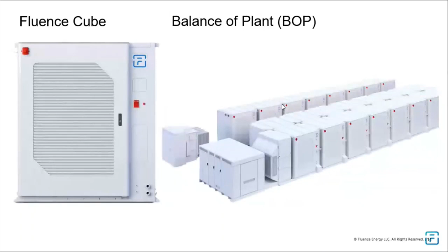And that's where battery storage comes in. What you're looking at is a Fluence battery storage solution. On the left is a cube - the box that has the batteries in it, along with the HVAC and firefighting equipment. On the right side is the balance of plant: besides the cubes, there's a telco rack which allows communication with the batteries, an inverter system which turns DC into AC power, and a transformer that raises the power to the voltage you require and feeds it into your operations.